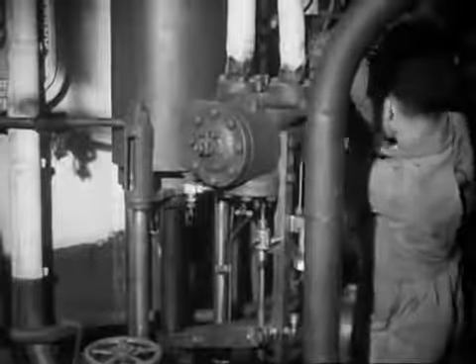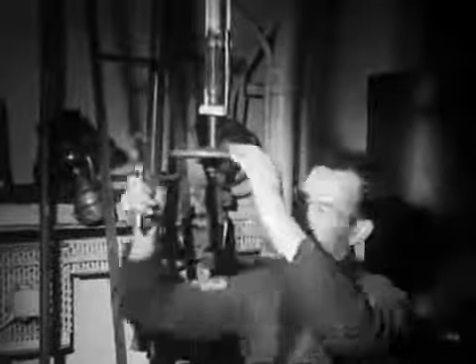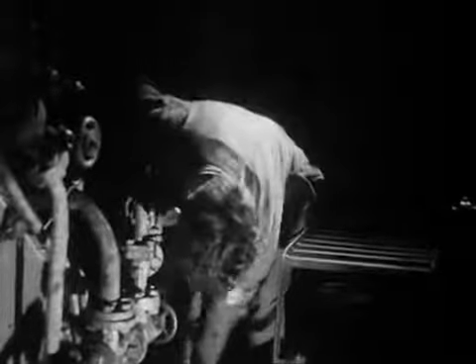used in boilers. When there's a sufficient head of steam, the main oil fuel pump, auxiliary feed pump and oil fuel heaters can be warmed through and started, not forgetting the fans which provide the air and draft. The superheater drains are now changed over to the steam trap from the bypass to avoid wasting steam. For instead of blowing it into the air by our atmospheric exhaust, we're going to put it through the cooler, condense it and use the water to make steam again. So we put the closed exhaust onto the feed heaters.